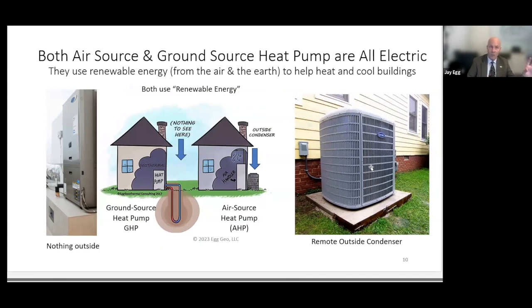What's different with a geothermal system is that, as you can see in this illustration, instead of having an outside condenser, it's got outside pipes hidden underground that are communicating with 55-degree earth temperature, rather than sub-freezing wintertime temperatures or 95, 100, 105-degree summertime temperatures. So it's not hard to see why the geothermal heat pump operates more efficiently — a 55-degree thermal energy source is much more abundant heat than 10, 15, or 20 degrees outside.